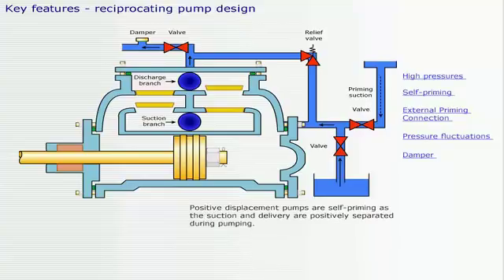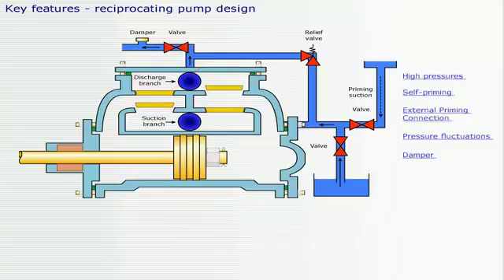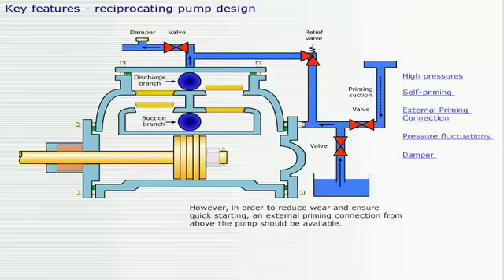Positive displacement pumps are self-priming as the suction and delivery are positively separated during pumping. However, in order to reduce wear and ensure quick starting, an external priming connection from above the pump should be available.